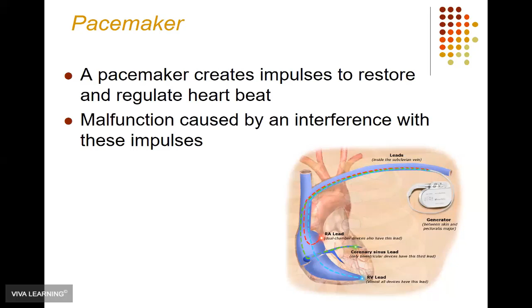The greatest risk of malfunction with pacemakers or ICDs is with electromagnetic interference. The electrical interference is interpreted by the pacemaker as cardiac electrical activity and may inhibit the pacemaker from functioning. This situation is temporary and does not usually cause permanent damage to the pacemaker.